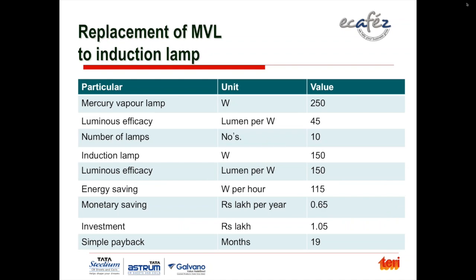Mercury vapor lamp, 250 watts. This is the lumen per watt efficiency, 45 lumens per watt. The number of lamps in the plant was 10. We recommended they be replaced with induction lamps of 150 watt rating. Luminous efficiency is 150 lumens per watt, very high compared to the 45, about 3 times that. Energy saving was 115 watts per hour.